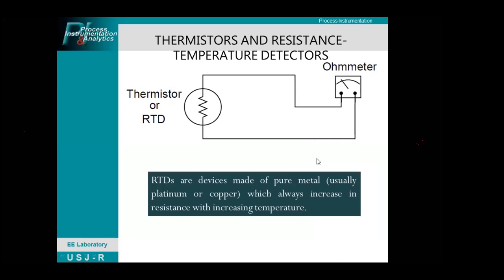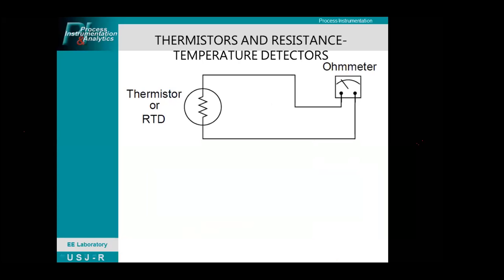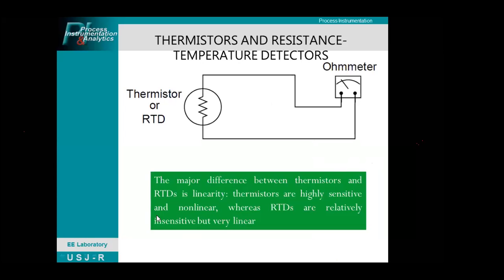So the RTDs are devices also made of pure metal, usually platinum or copper, which always increase in resistance with increasing temperature. Then the major difference between thermistors and RTDs is linearity. Thermistors are highly sensitive and non-linear, whereas RTDs are relatively insensitive but very linear. Okay, so that's the difference between the thermistors and RTD.